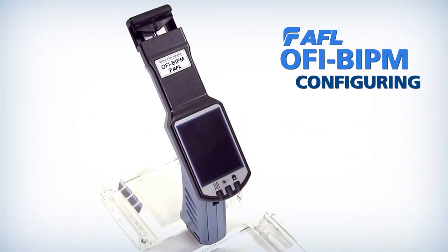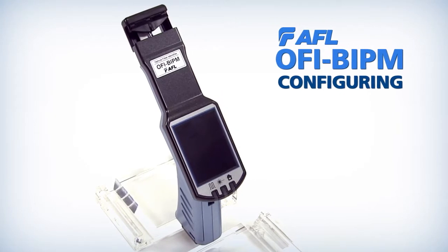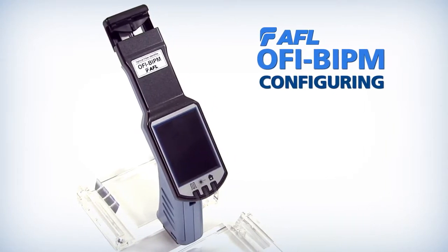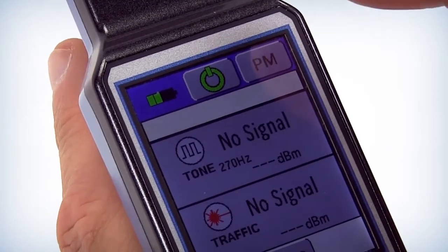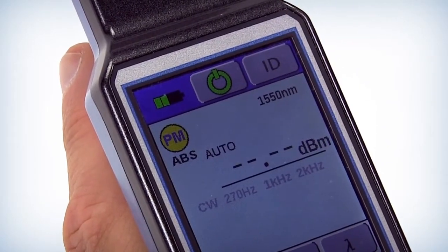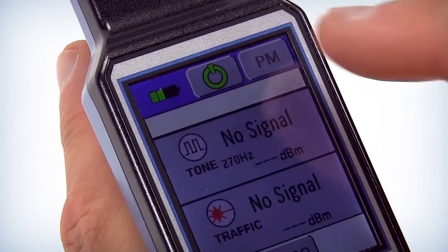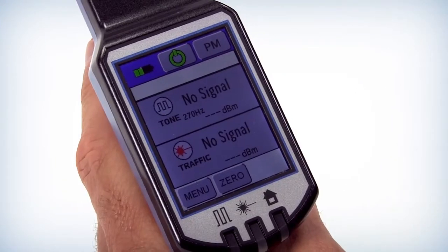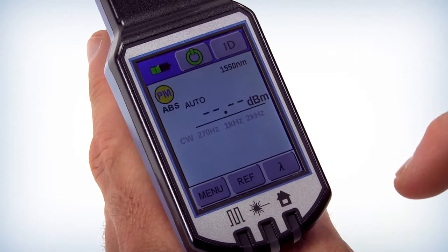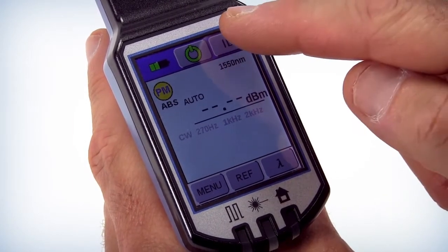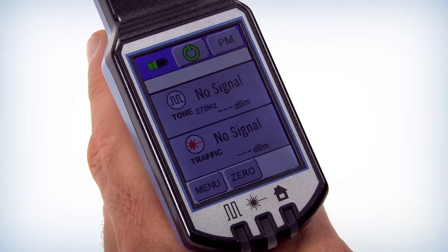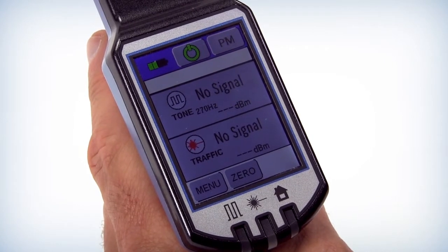The next step is how to configure AFL's Optical Fiber Identifier OFI-BIPM. From the touch screen you should place the unit in the appropriate mode by toggling the button in the upper right hand corner of the screen. The PM button changes the power meter and the ID button changes the identifier mode. In the lower left corner of the screen is the menu button which is used to configure the device.